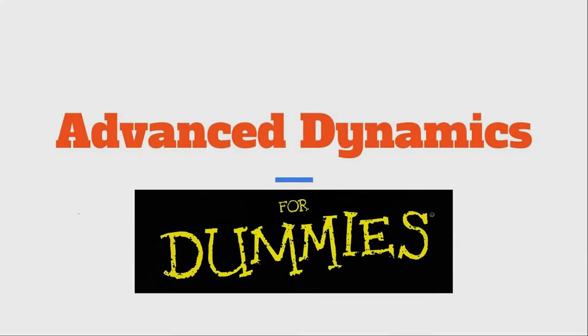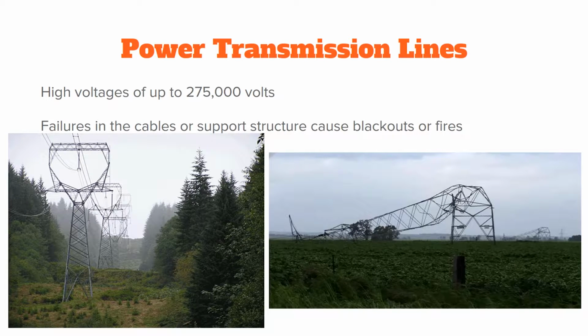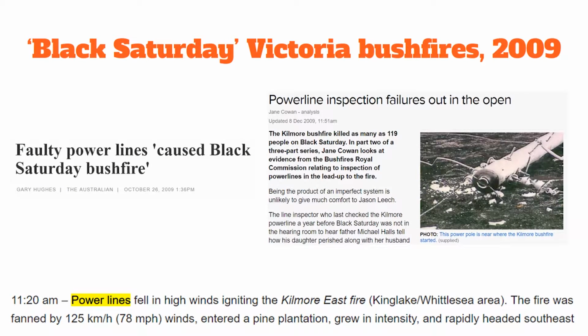Welcome to Advanced Dynamics for Dummies. For this week's project, we investigate a method for reducing Aeolian vibration in power lines. Power transmission lines carry high voltages of up to 275 kilovolts through steel cables suspended by support towers. With high voltages comes a high danger factor, as a fault in these lines can cause shorts, blackouts, and potentially fires. A terrifying example of this is the Black Saturday bushfires in Victoria, where vibration led to the fatigue failure of power lines which sparked fires.